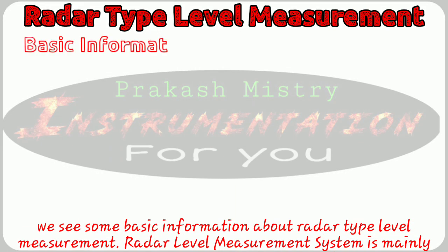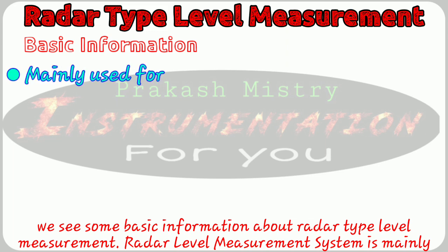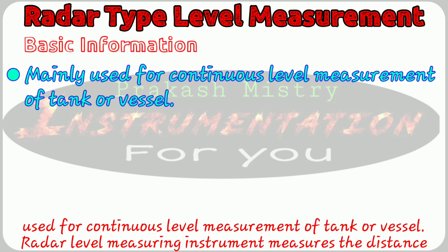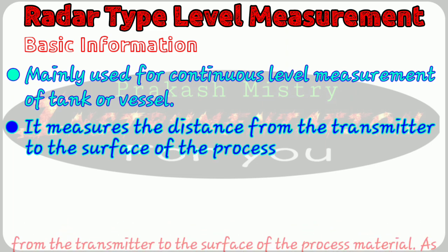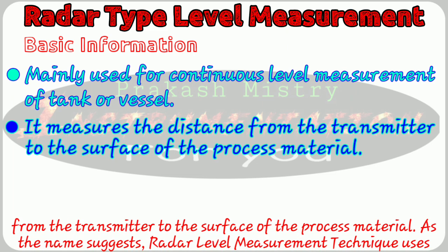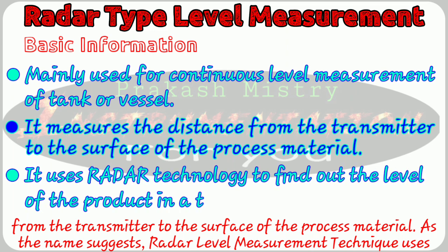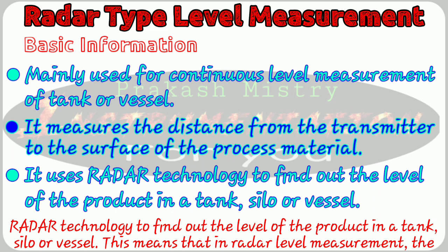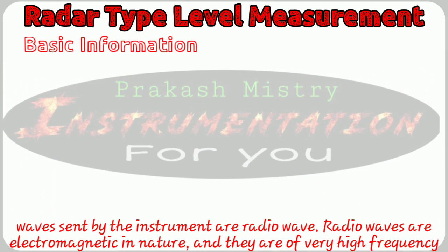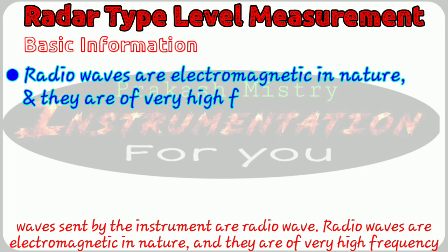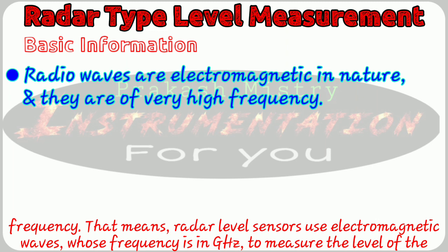Let's first see some basic information about radar type level measurement. Radar level measurement system is mainly used for continuous level measurement of a tank or vessel. Radar level measuring instruments measure the distance from the transmitter to the surface of the process material. As the name suggests, radar level measurement techniques use radar technology to find out the level of the product in the tank, silo, or vessels. The waves sent by the instrument are radio waves, which are electromagnetic in nature and very high frequency.